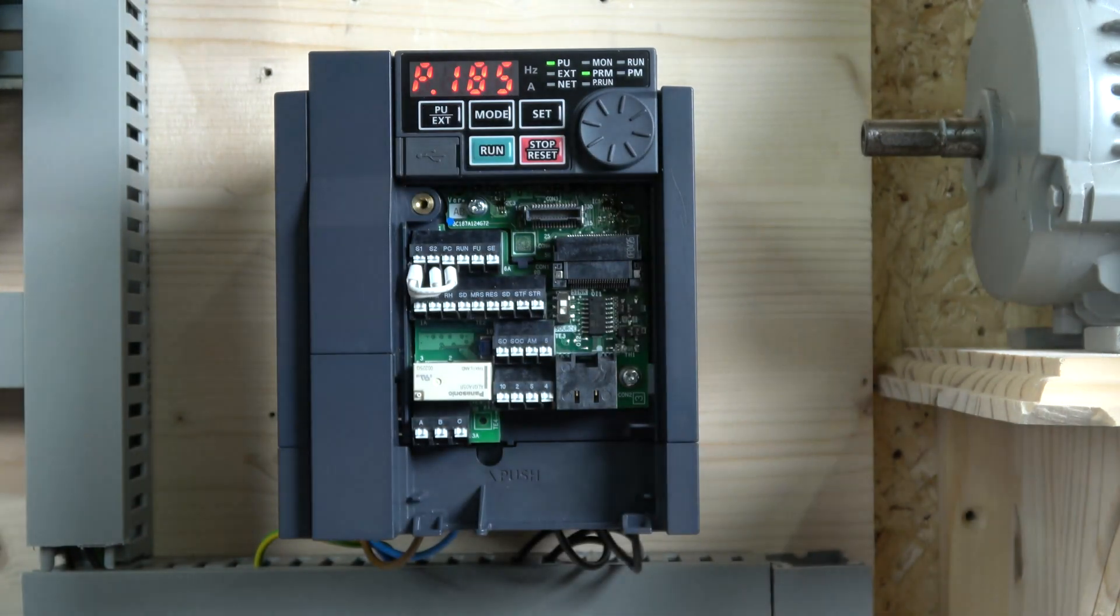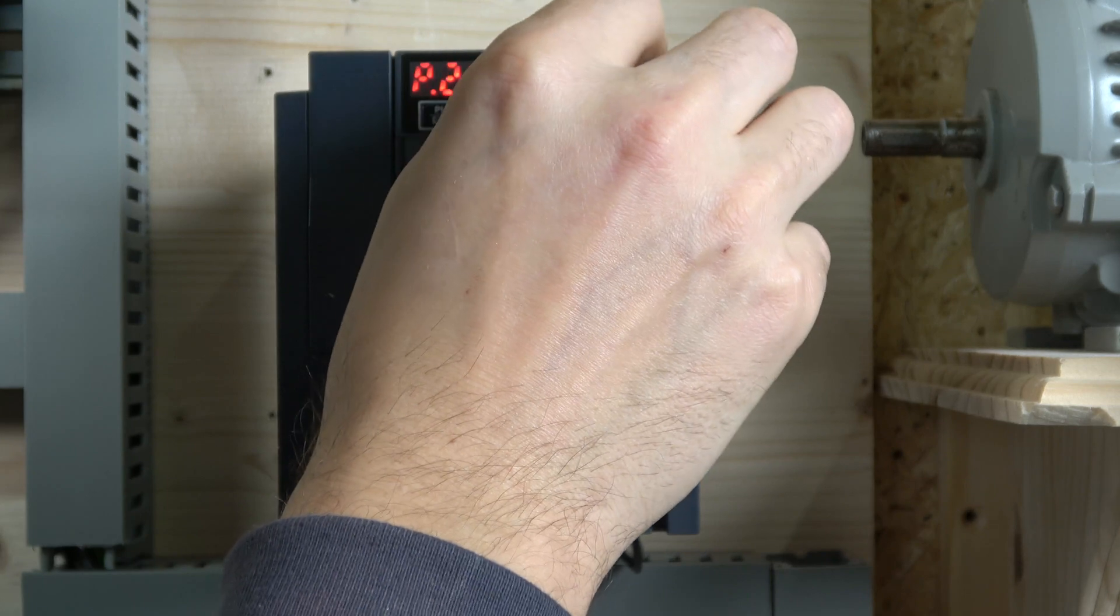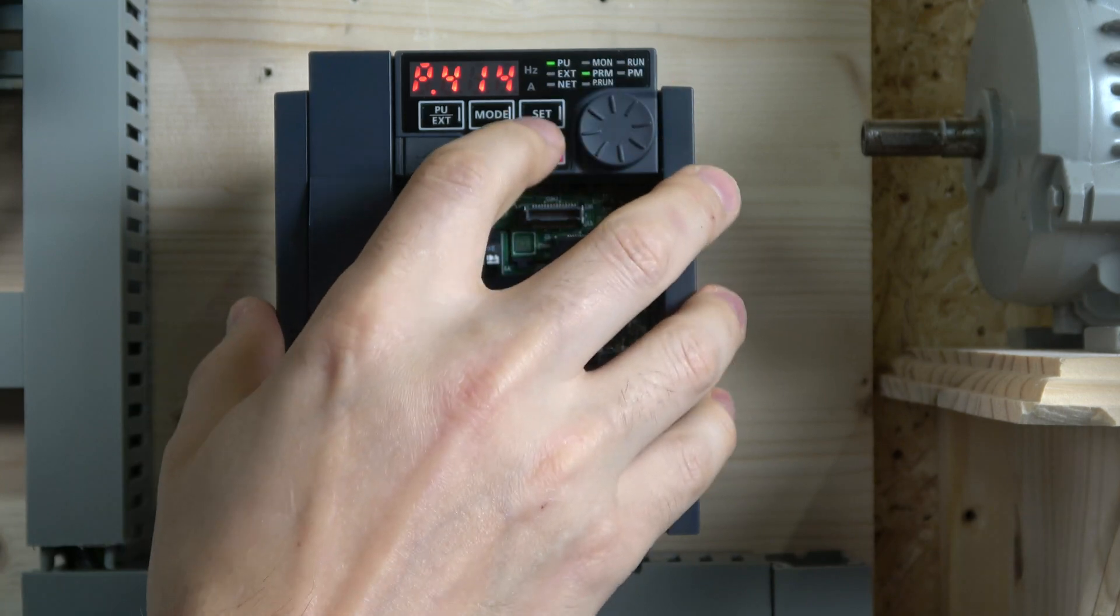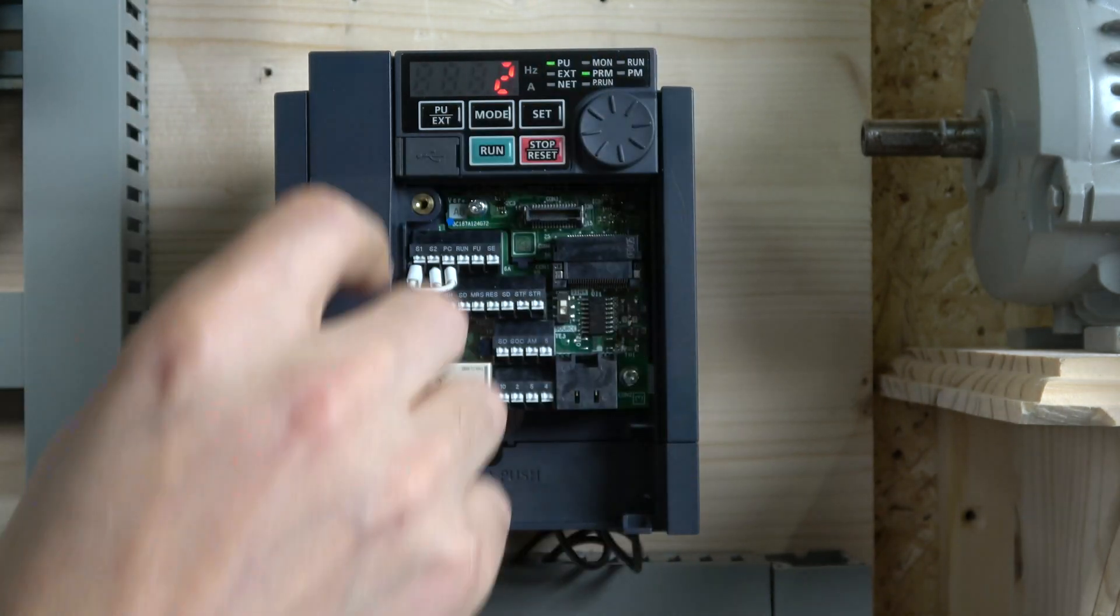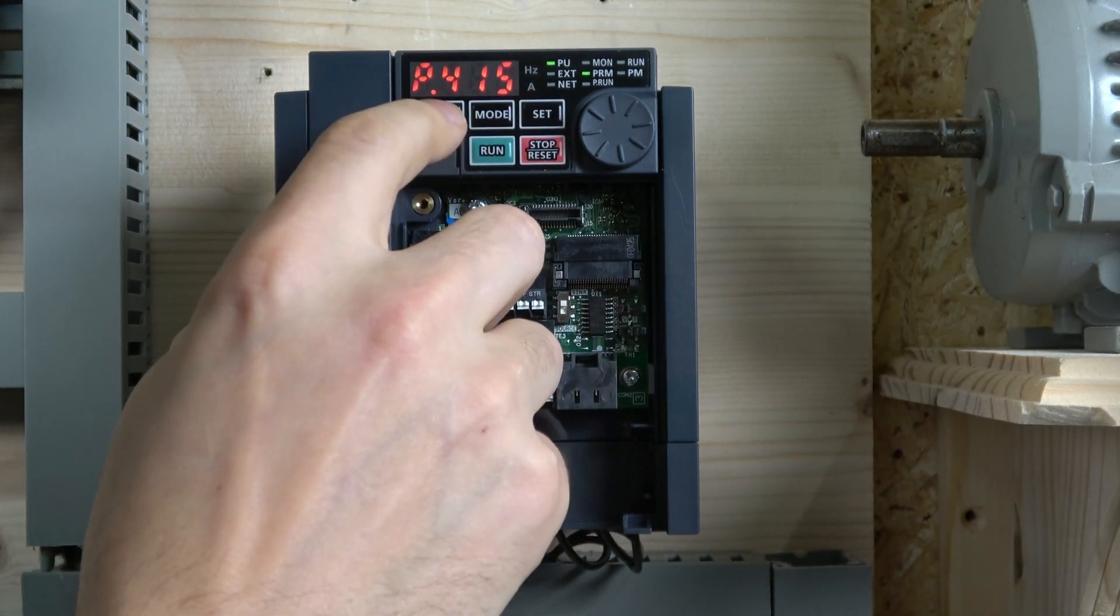Next is 340, where we're selecting to work in network mode. We select that to 2. And last but not least is our PLC functionality, parameter 414. We need to make sure that's set to 2, already by default. Excellent, that's done.